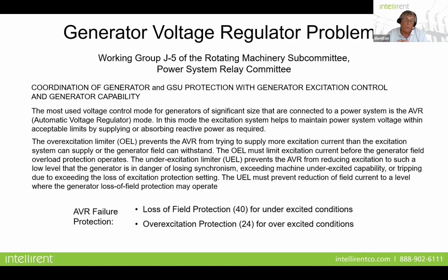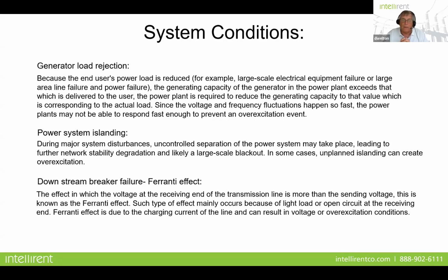So AVR protection in a generator comes in two forms: loss of field protection, which is for underexcited conditions, because that can be damaging as well, and overexcitation protection for these conditions that we're going to set in the transformer relay itself. Now, the point that I want to make is you can have overexcitation conditions in EHV or in a transmission system. And what would cause that? Well, generator load rejection. On a large scale electrical equipment failure or a large area line failure and power failure, basically the generating capacity of the generator in the plant exceeds what is being used. The power plant at that point is required to reduce the generating capacity to that value. But since the voltage and frequency fluctuations happen so fast, the power plants may not be able to respond fast enough, and you can have an overexcitation event.